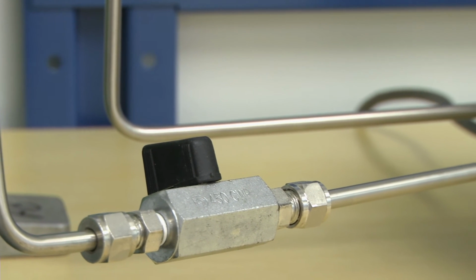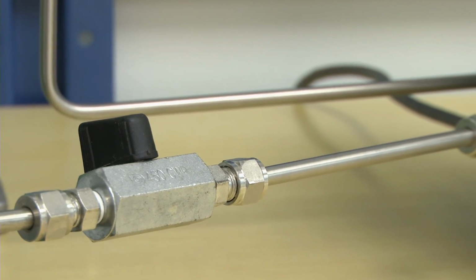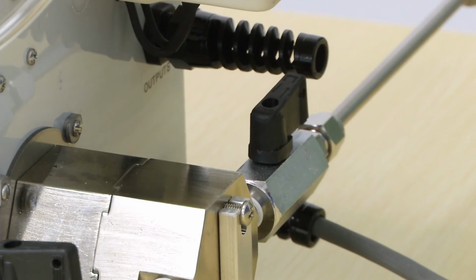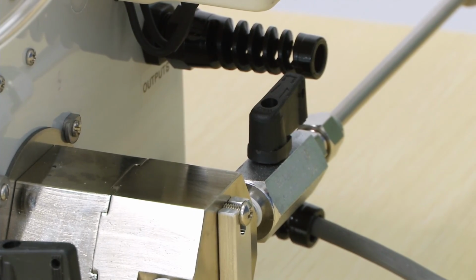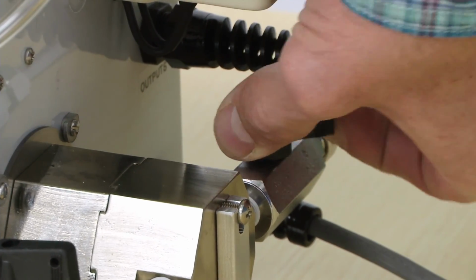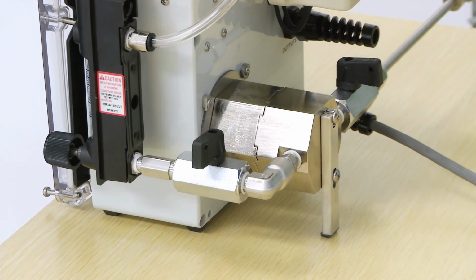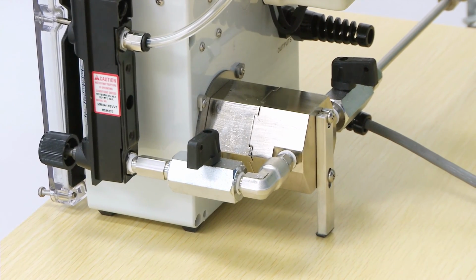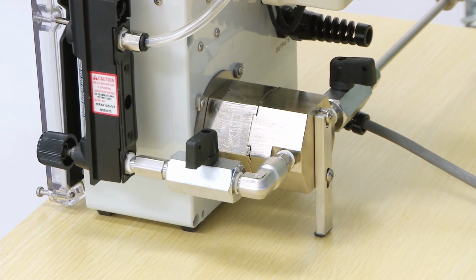For the procedure we just performed, we used gas that was under positive pressure. Consequently, we highly recommend that the upstream valve be closed first, followed immediately by the downstream valve as shown. This will help avoid an inadvertent overpressurization of the sensor.